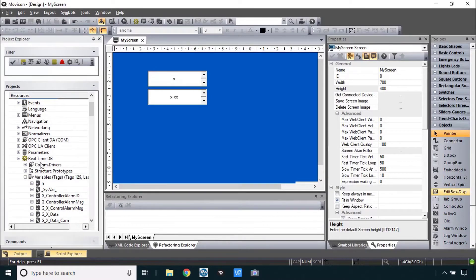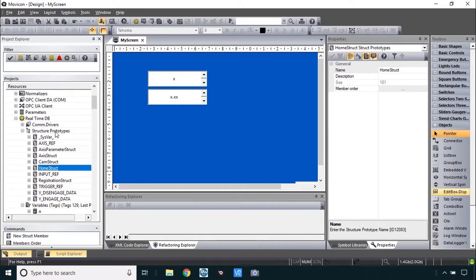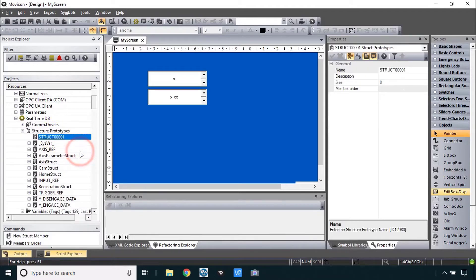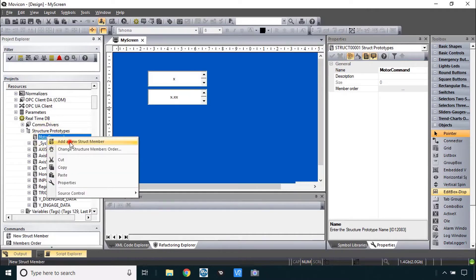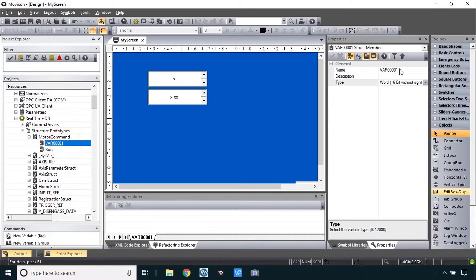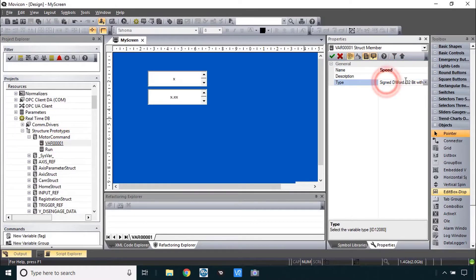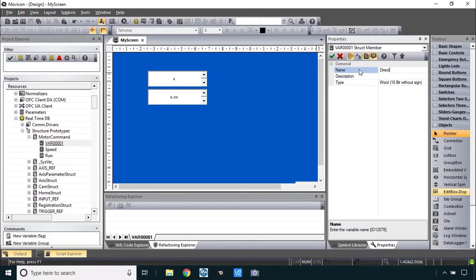Back in the project, under real-time DB you can see the structure prototypes. Except for sysvar, the majority of these were imported when we imported the variables at the very beginning of the class. Let's make our own: right-click, new structure definition, and I'll call it 'motor command'. Right-click to add structure members — a 'run' command of data type bit, a 'speed' member of data type float, and a 'direction' member — for example forward, reverse, shortest path, previous direction — which needs a byte.